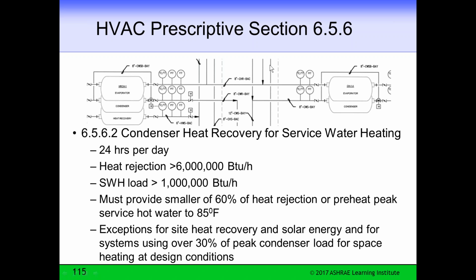Now, since I work on it, I could maybe raise the thing saying, well, service water heating is not the same thing as this process water. But being an engineer, I could argue with myself, but wait a minute, I'm using it to wash the equipment down. It's not really in the process, it's in the cleanup, which is exactly what service water heating is. So I didn't want to use heat recovery on that project because obviously I have a giant peak only one time a day, but I had to work my way around and out of the problem.